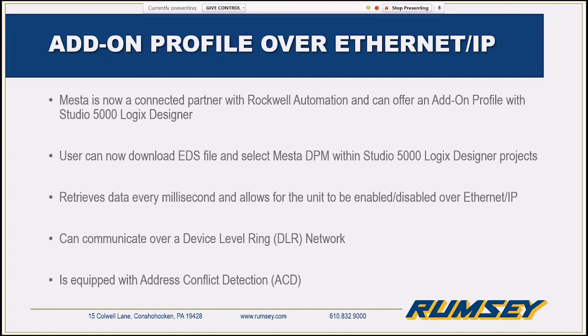What it does is, you can select the active filter, and it'll auto-populate 51 different data tags for you so that you don't have to deal with all of that when you're integrating the unit into your system. We can also communicate over a device-level ring network, and we are equipped with address conflict detection. So if there's ever a time when multiple pieces of equipment are given the same IP address, we can help to determine that problem and reassign an IP address.